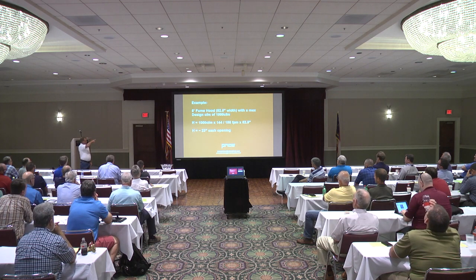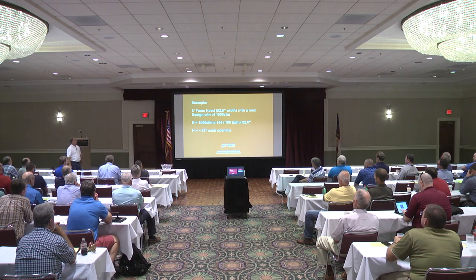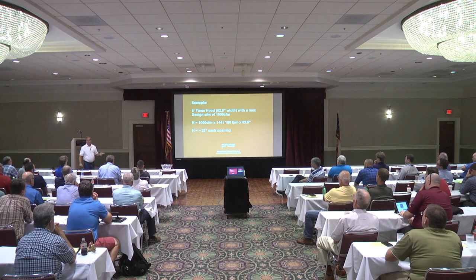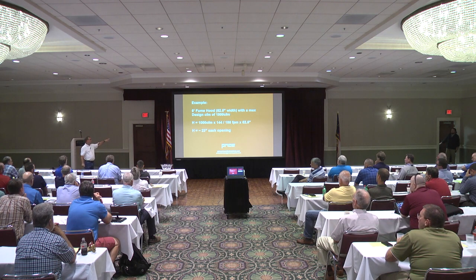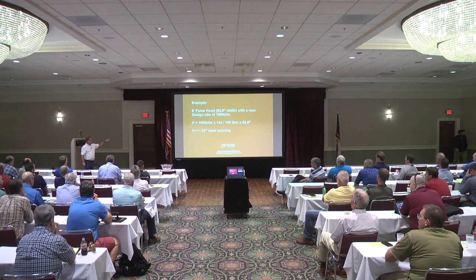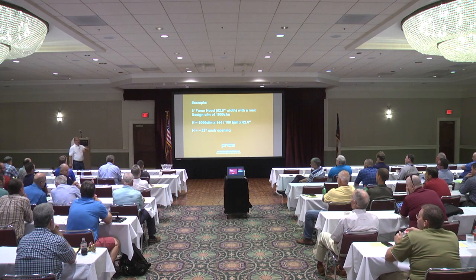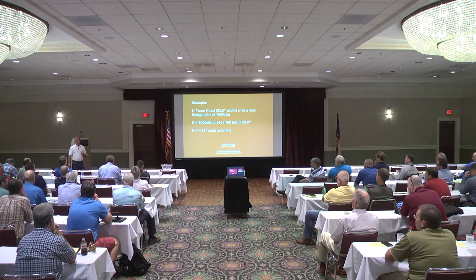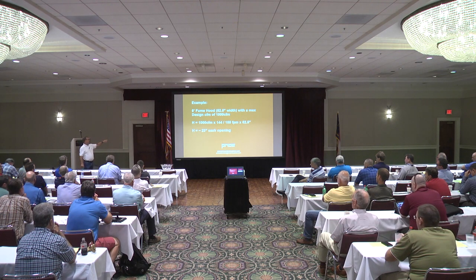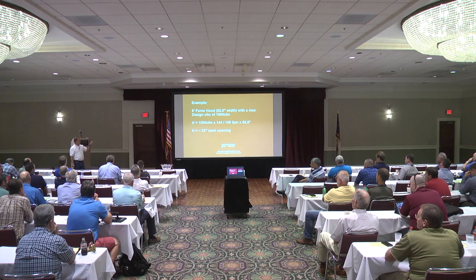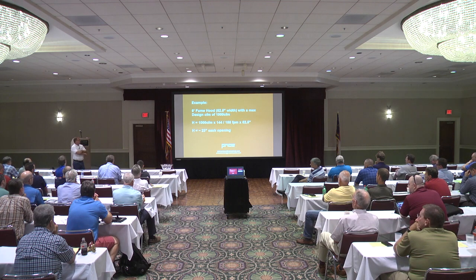Example, a 6-foot hood, 62.5 inches wide, maximum design CFM of 1,000 CFM. 1,000 CFM times 144 divided by 100 feet per minute, divided by 62.5 inches, is 23.1 or so, roughly a 23-inch sash opening. That's not 18, that's not the sash stop, that's not anything but what the design engineer said he wanted. He wanted 1,000 CFM on that hood. You have to go to 23 inches to get that hood at 1,000 CFM. If you don't, you're going to send the report back through the channels. It's going to come back to me, and you're going to say I'm low. I'm not low. We didn't initiate the sash at the right height to give you the flow associated with that 6-foot hood at 1,000 CFM.